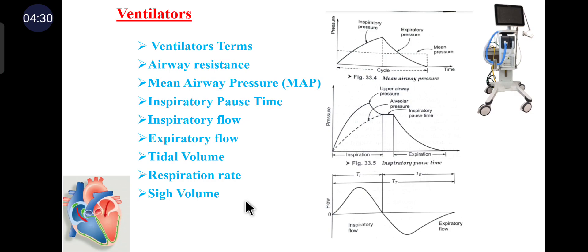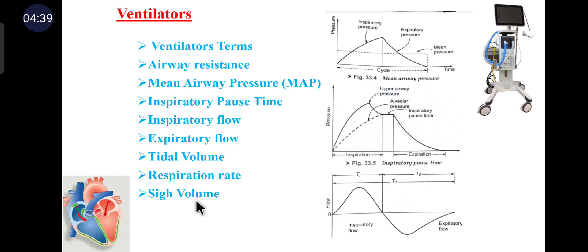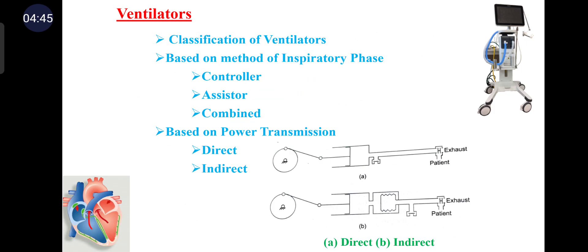Sigh volume is defined as 150 percent of the set tidal volume. Based on the tidal volume, we can calculate the sigh volume. Ventilators are classified by various methods based on the method of the inspiration phase: controller, assistor, and combined.